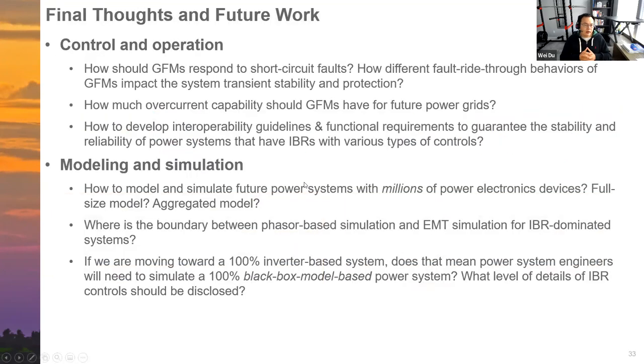So finally, I'd like to share some final thoughts. I think there are still a lot of things that need to be studied for grid-forming inverters. From the control and operation perspective, how should grid-forming inverters respond to short circuit faults? And how do different fault ride-through behaviors of grid-forming inverters impact the system transient stability and the protection? It's not just about current limiting, it's also about the system level stability and protection. It's a very important topic we should study.